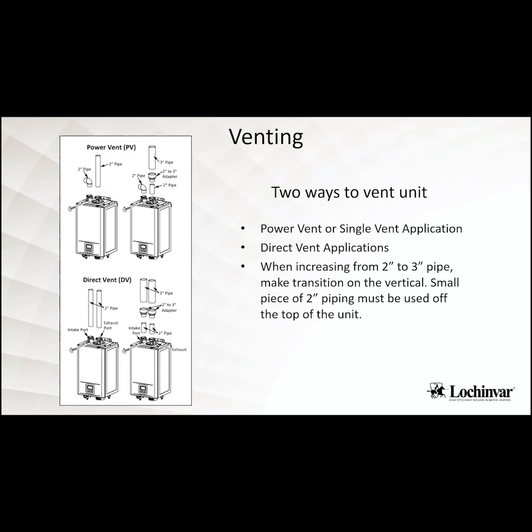But if you are going to go to 3-inch, make sure you're doing that on the vertical, not on the horizontal, because we do want that pipe graded back to the unit. So the condensate that's in that line is going to drain back to that unit. If you do that 2 to 3 increaser on the horizontal, you're going to create a big pool of condensate in there, and you could see some error codes flashing down the line on that.